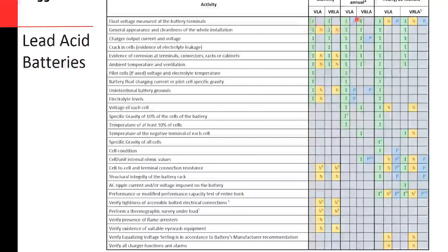This shows, for example, the float voltage measurement at the battery terminal. So you can see here IEEE requires that for vented lead acid batteries and valve regulated batteries monthly, and obviously triannual or quarterly. And NERC, as we were saying, requires it every 4 months. It's also required in NETA every 18 months or yearly. So this table will indicate pretty quickly what the requirements are in all of the standards.